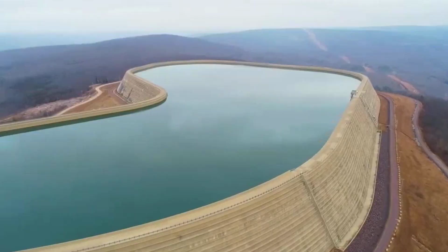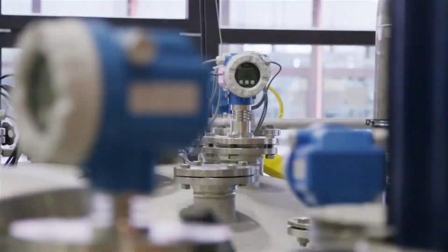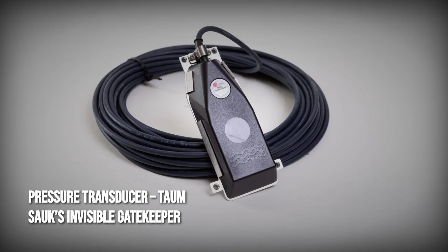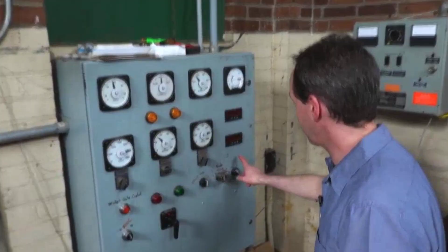At Taum Sauk, the physical safety of the reservoir depended almost entirely on its electronic nervous system. Instead of a concrete spillway or overflow channel, engineers installed a suite of sensors to monitor the water level. The main measurement came from pressure transducers mounted inside conduits that were strapped to steel cables running down the inner slope. These sensors converted water pressure into digital readings, feeding a programmable logic controller that started and stopped the massive pumps. Every fill cycle, operators in a remote control room relied on those numbers to decide when to halt pumping, trusting the sensors to reflect reality at the top of the mountain.